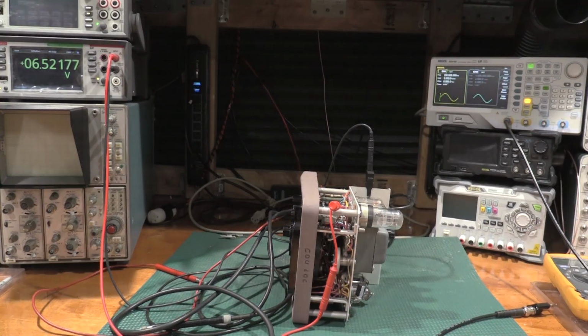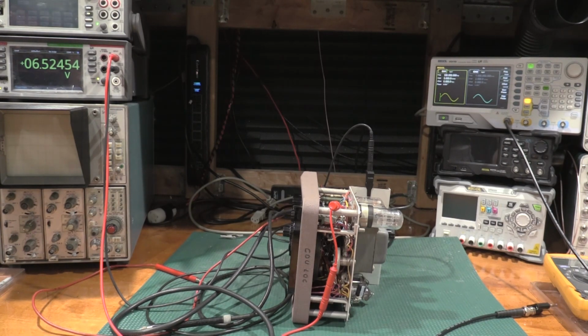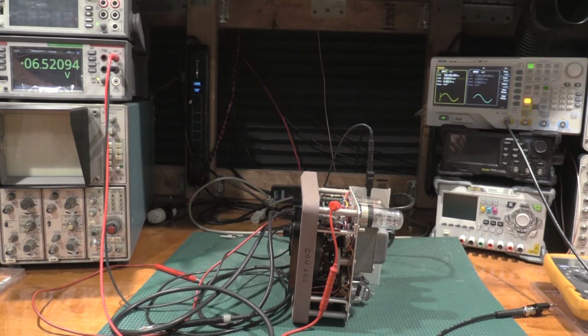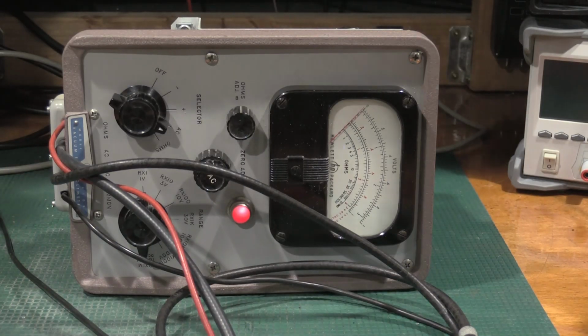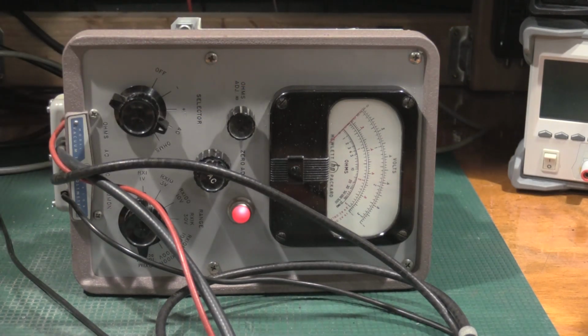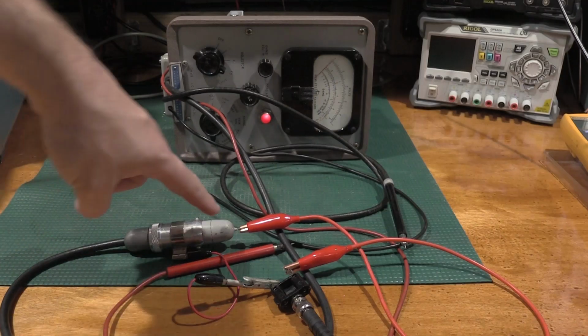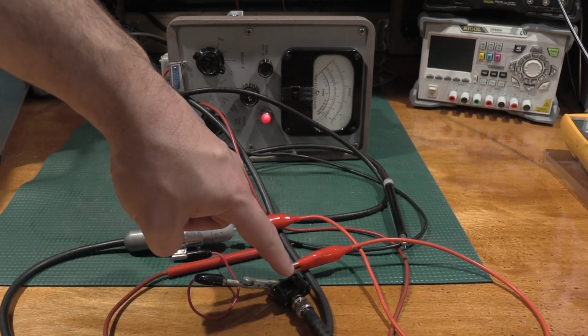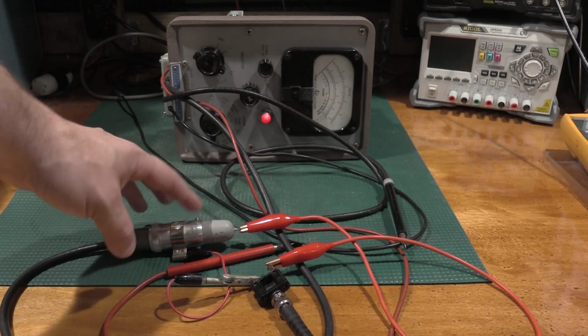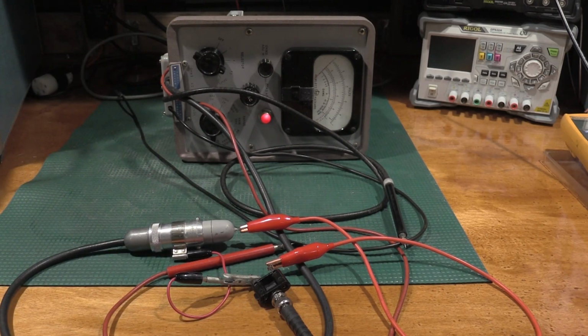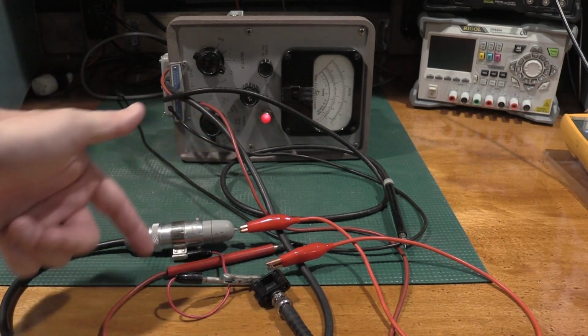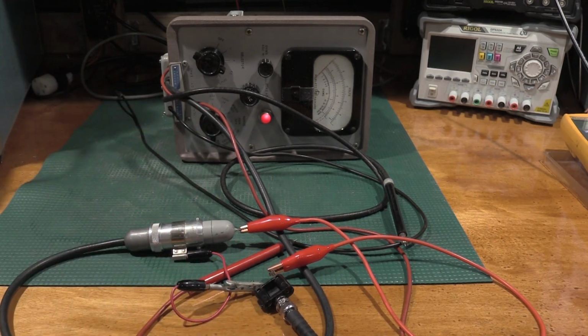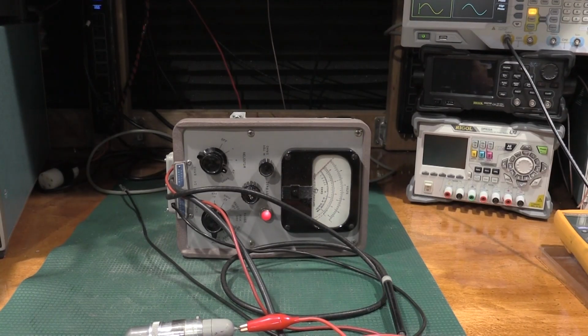Okay, it did stabilize a bit high, but I knocked it back down to 6.52. So let's see what AC measurements look like. I have the function generator hooked up for 1 volt RMS because this is an RMS meter. 1 volt RMS out of the Rigol 4162 into the probe tip from this BNC connection, and then we have ground. So the outer shell of the probe is chassis ground of the meter, so common doesn't even need to be hooked up. Now this lead is really important when it comes to high frequency measurements because it's connected like an antenna. If we get meter deflection when I turn the output on, that's a really good sign.